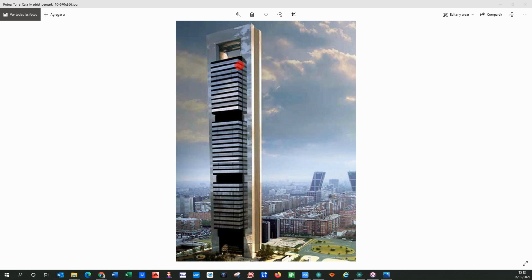And the second thing, and this is very interesting, is for the integrator. Every single semi-floor has 9 shutter actuators, 4 channel, and 4 DALI gateways. Exactly the same 68 times. So from the ETS point of view, we only did one single project, and we replicated exactly the same project 68 times. Because the IP of every IP router is different, we can retain the group addresses.